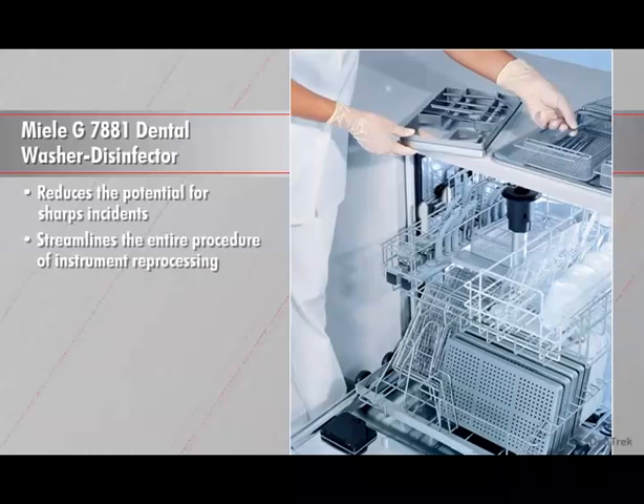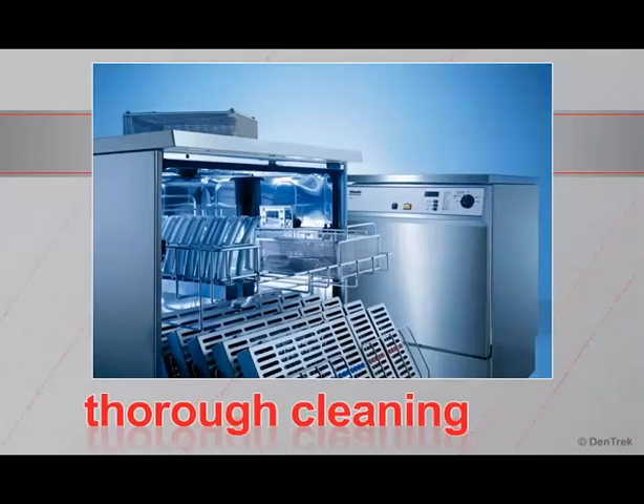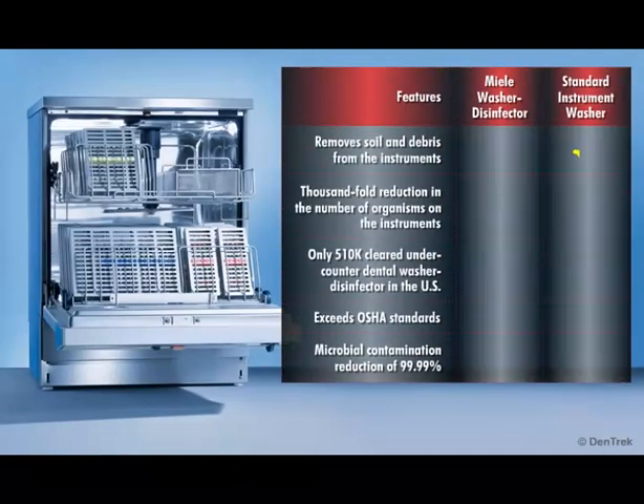It streamlines the entire procedure of instrument reprocessing while ensuring maximum safety for staff and patients. With its quiet performance and thorough cleaning abilities, the Miele G7881 is the only step you need prior to sterilization. A washer merely removes soil and debris from instruments. A washer disinfector removes soil and debris while also providing a thousand-fold reduction in the number of organisms on the instruments. The only 510K-cleared undercounter dental washer disinfector in the US, the Miele G7881 not only exceeds OSHA standards but also provides an industry-leading high-level disinfection with a microbial contamination reduction of 99.99%.